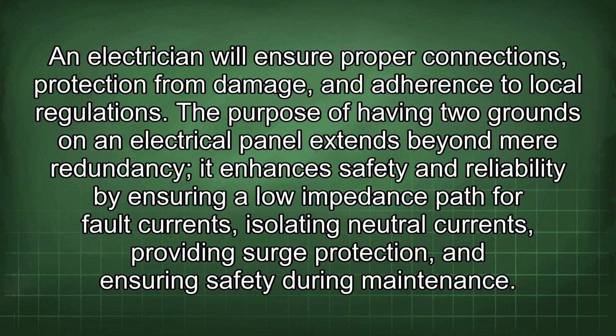The purpose of having 2 grounds on an electrical panel extends beyond mere redundancy. It enhances safety and reliability by ensuring a low impedance path for fault currents, isolating neutral currents, providing surge protection, and ensuring safety during maintenance.